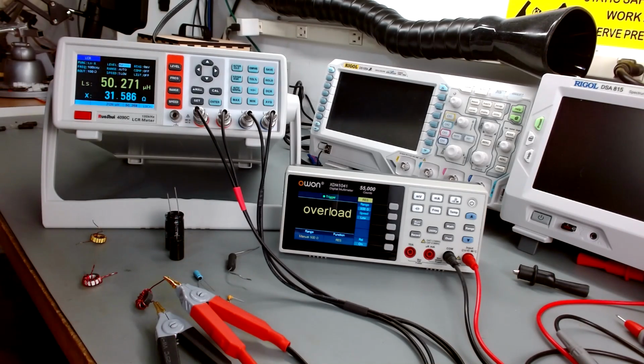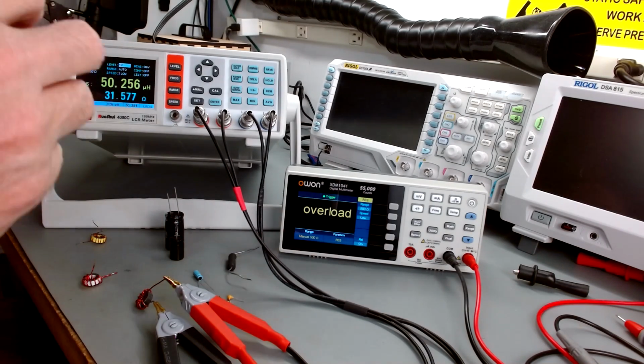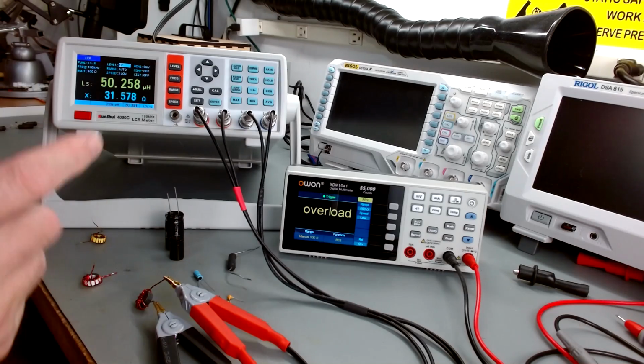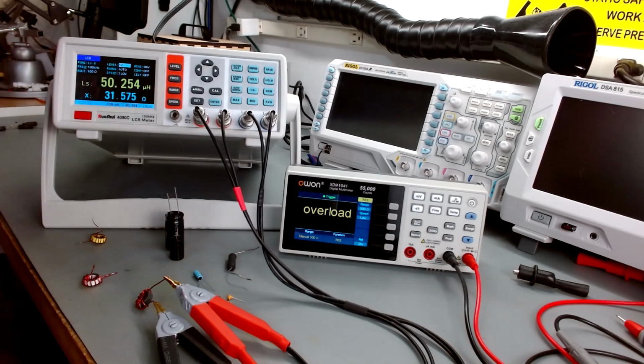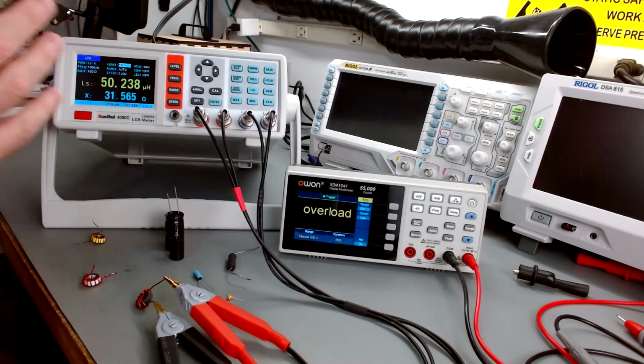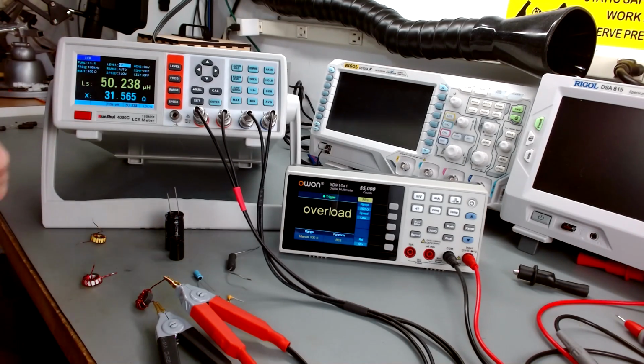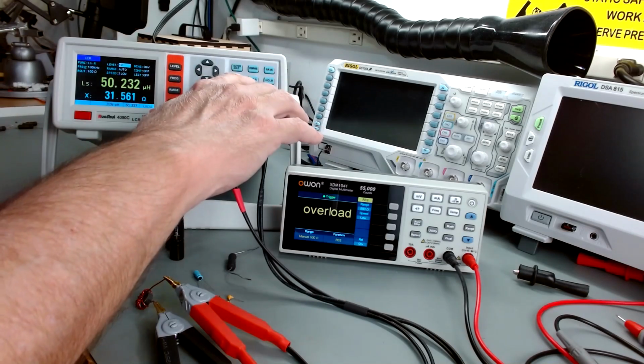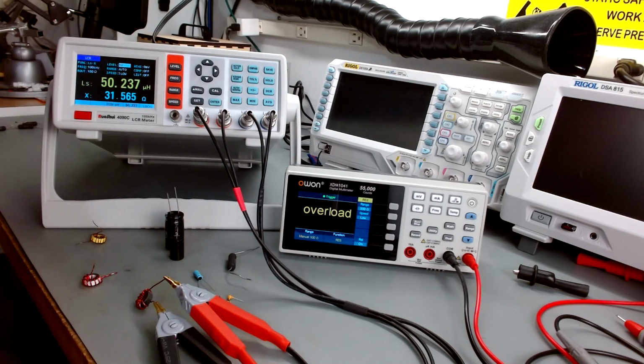The other thing you can do is set up compare, where you can put one device under test, disconnect and hook to another device, and it will compare the two and give you the differences. That's the compare button over here. It'll give you the differences of the two to tell you how much they vary. You can set up pass-fail, so you can put tolerance levels in and have it give you a pass-fail when it's testing things. So that's all kind of neat.